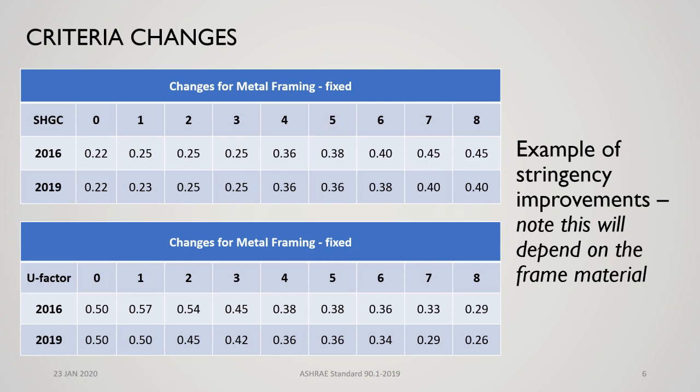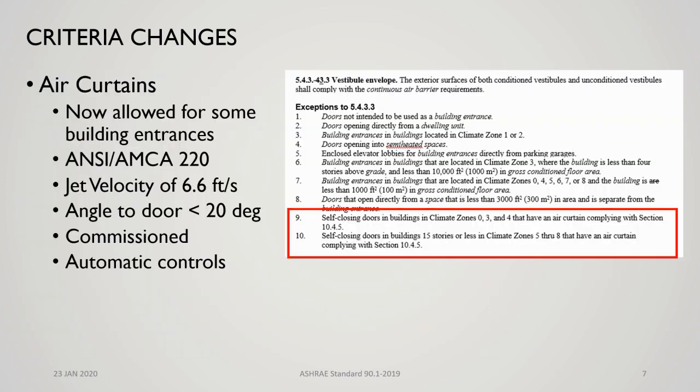We're still limited to 40% window wall ratio within the compliance path here. But that window type will drive a lot of your energy use, and is a part of the trade-off that you use for Chapter 11, even 5.6, ComCheck, and Appendix G.